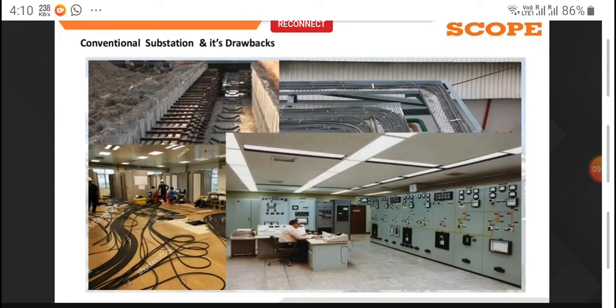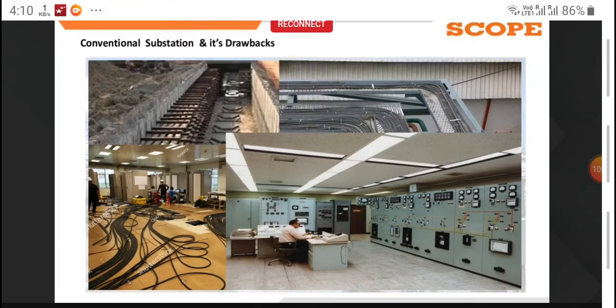My topic starts with how substations have evolved. Decades ago, substations were conventional substations. You can see big, very huge control panels, huge protection panels, and a lot of cables running from the substation to the control room. The cables ran through trenches, through walls, through the ground, and we used to see all of this in conventional or old substations. Even today, mostly 50% to 40% of substations are conventional. Conventional means there is no automation; everything is a manual system.